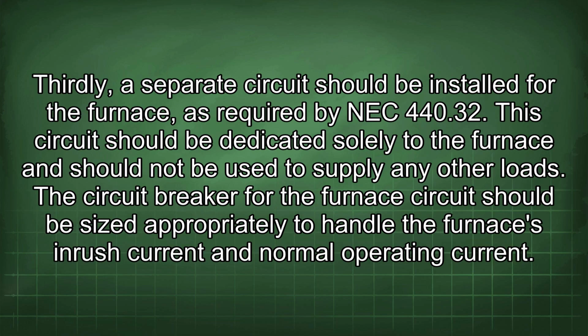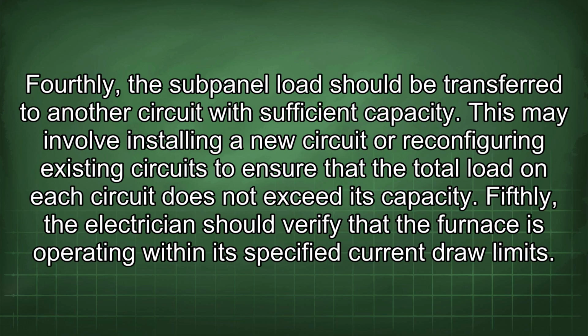Thirdly, a separate circuit should be installed for the furnace, as required by NEC 440.32. This circuit should be dedicated solely to the furnace and should not be used to supply any other loads. The circuit breaker for the furnace circuit should be sized appropriately to handle the furnace's inrush current and normal operating current.